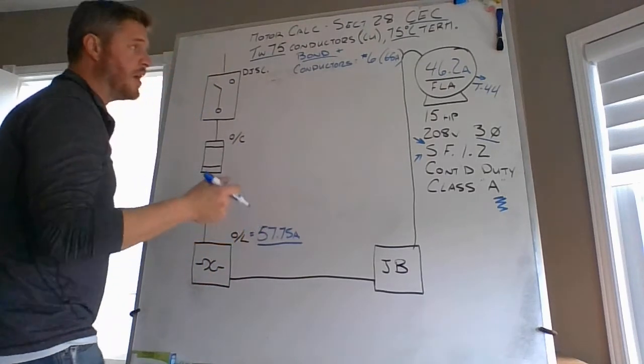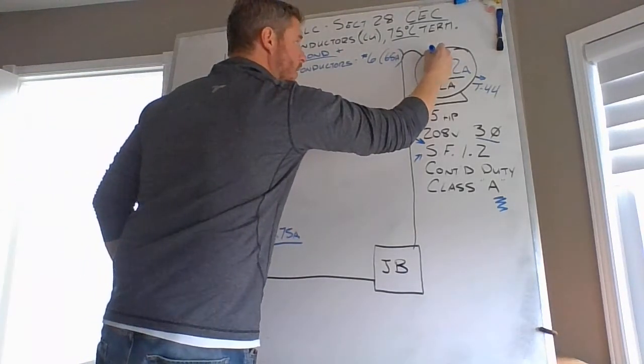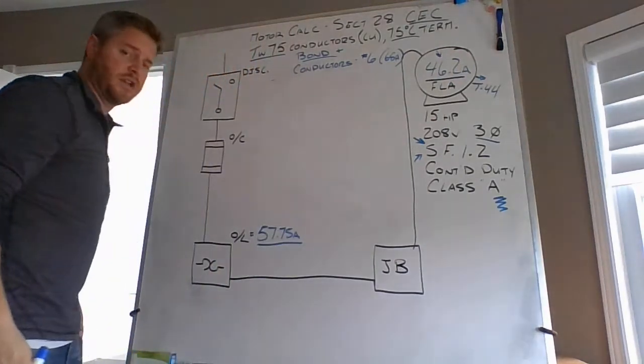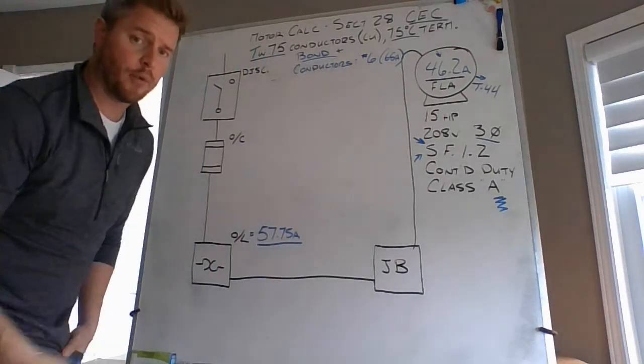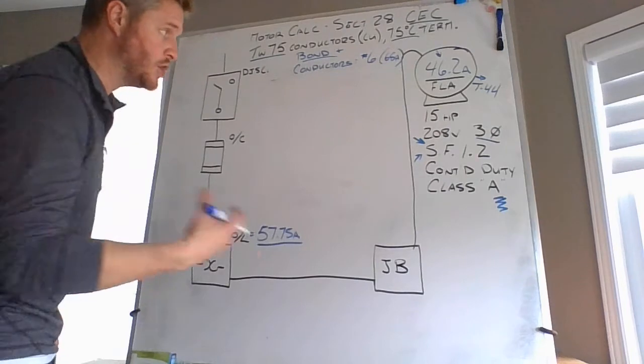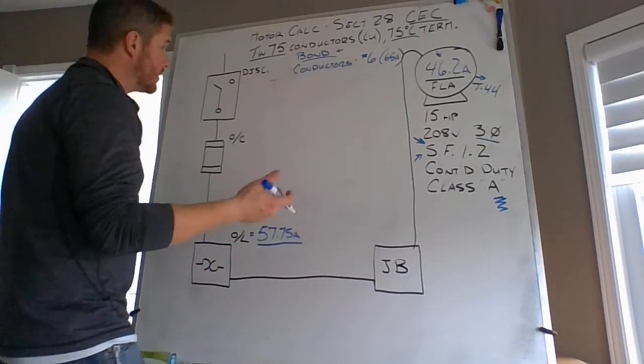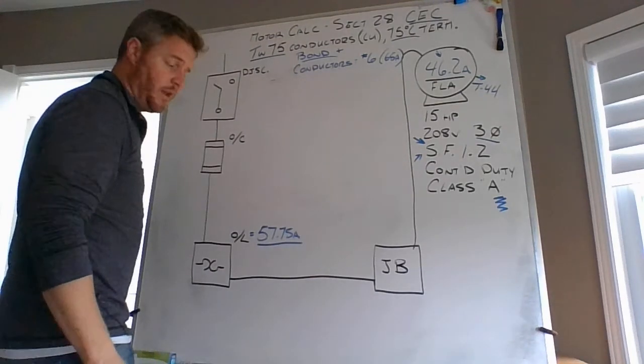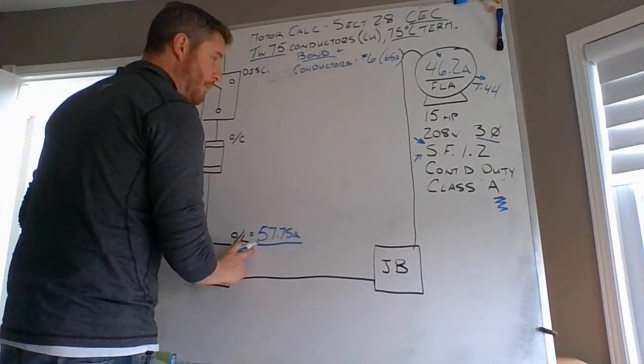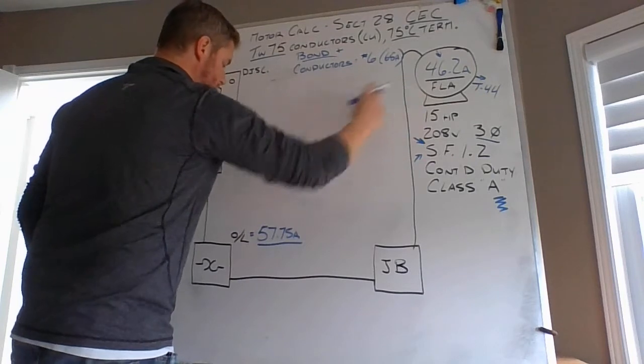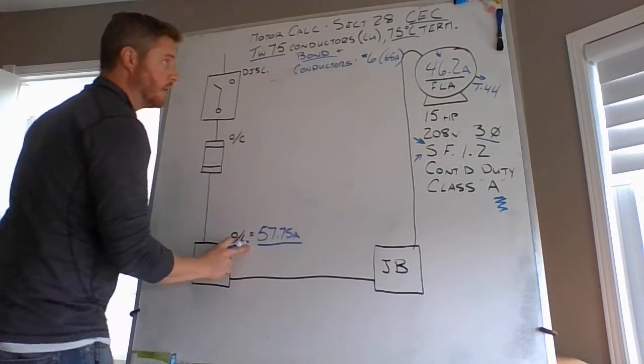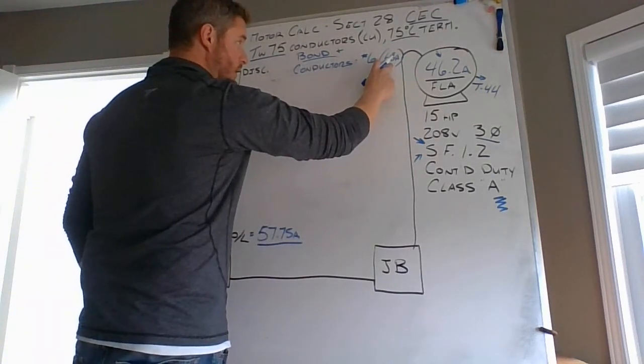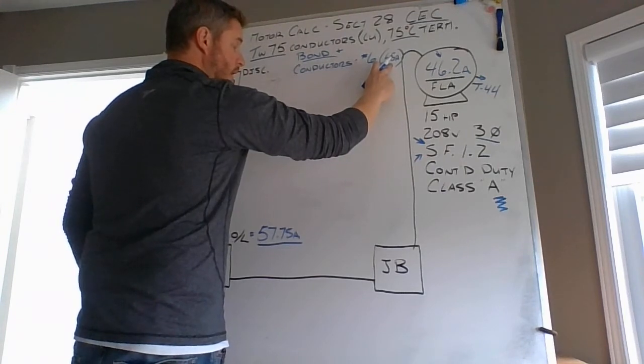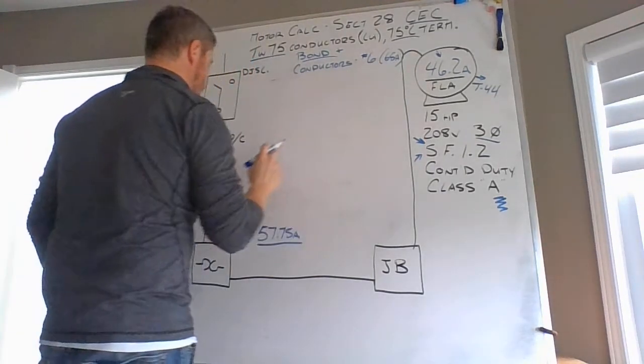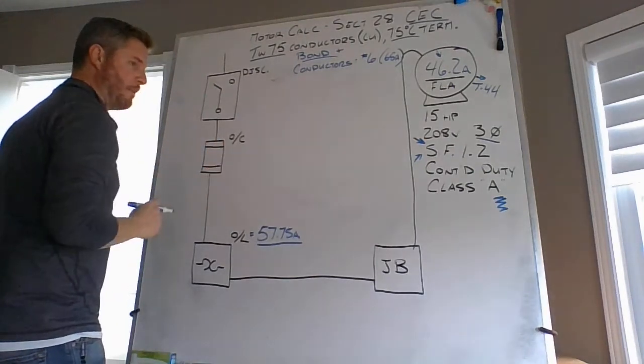But in normal operation, you still have to look at this number, the 46.2 amps. In normal operation, that 15 horsepower motor at 208 volts should realistically never draw more than 46.2 amps. So your overloads are there as a backup, just in case your motor fails. But then your overloads are also observing the capabilities of your conductor. And what motor control won't show you is your overcurrent capabilities.